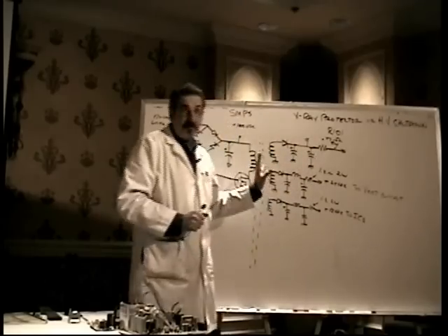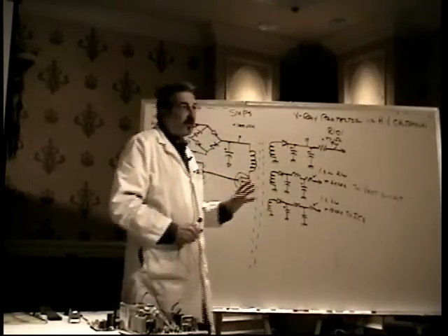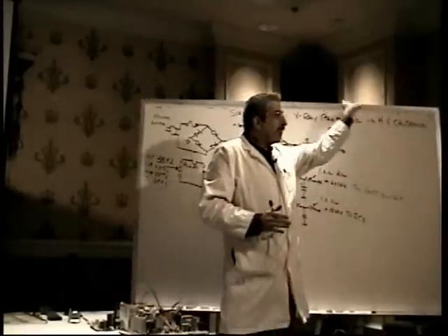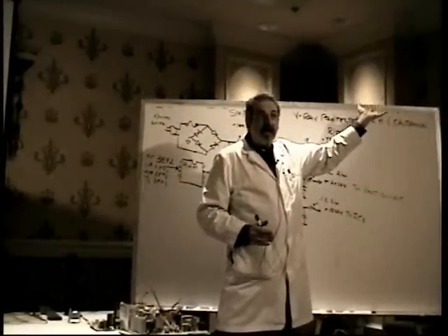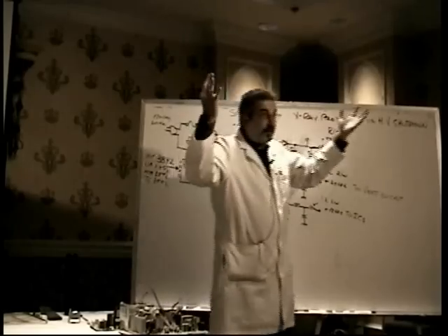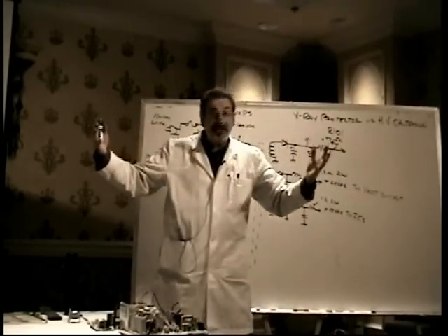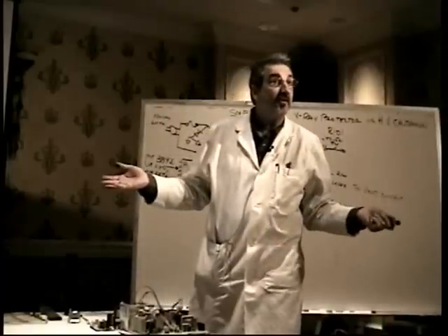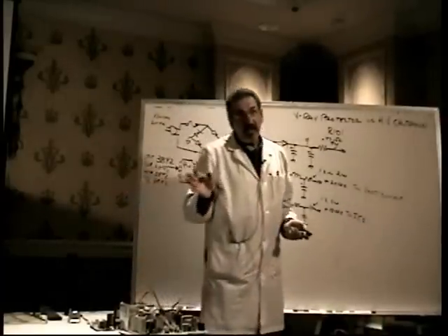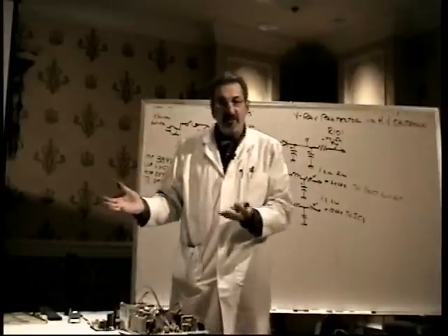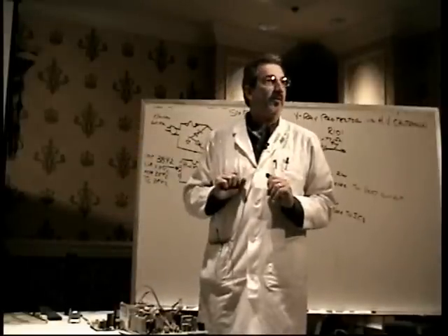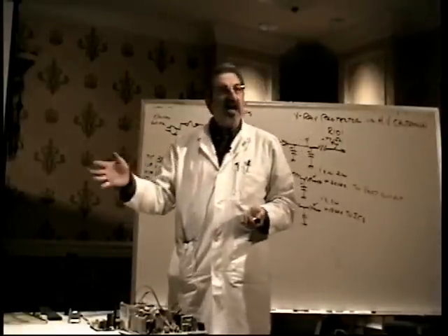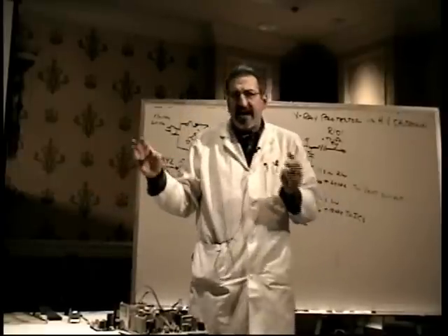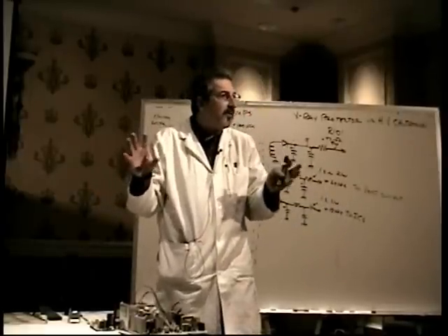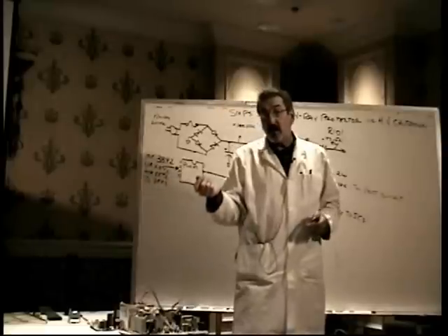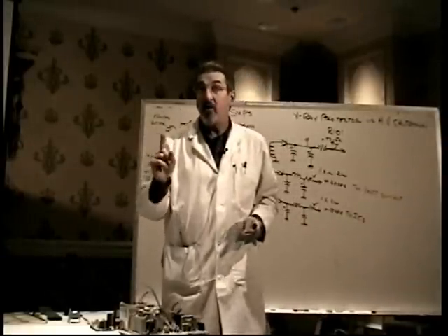Well, it's a power supply failure. If the power supply fails in any way such that the B plus output rises too high, all the voltages will be too high, of course, including the high voltage, the EHT, and then the monitor shuts itself down. The symptom is really interesting. The monitor comes on for a split second and then shuts itself down. It's not on long enough for you to see any kind of an image. But you know how you can hear that static sound that monitors make when they first come on? You hear that sound, and actually you hear it really loudly.